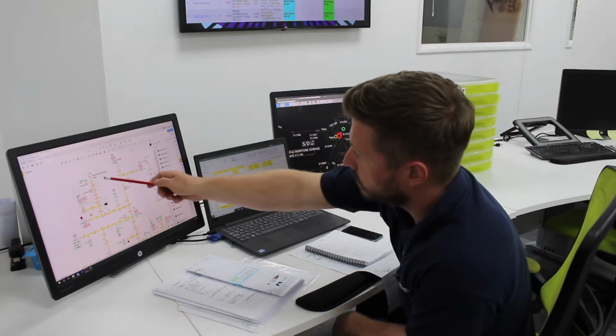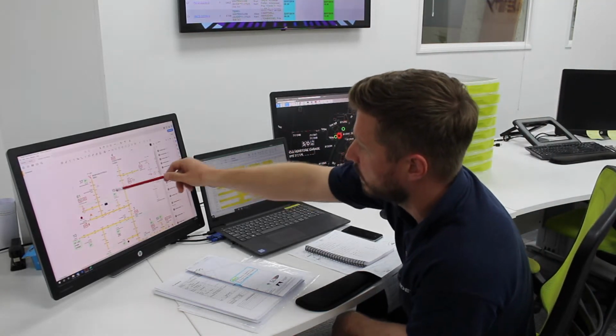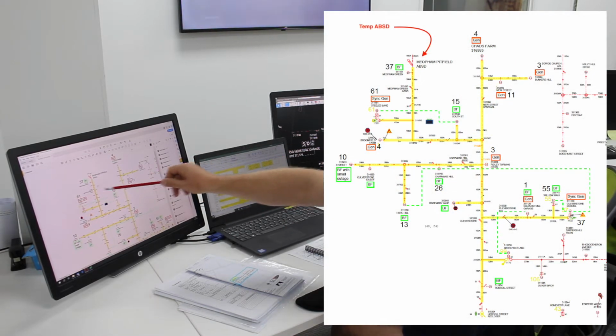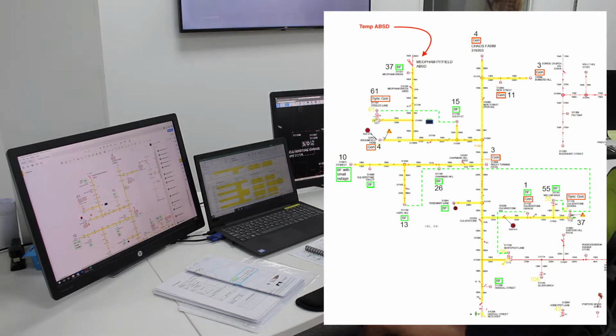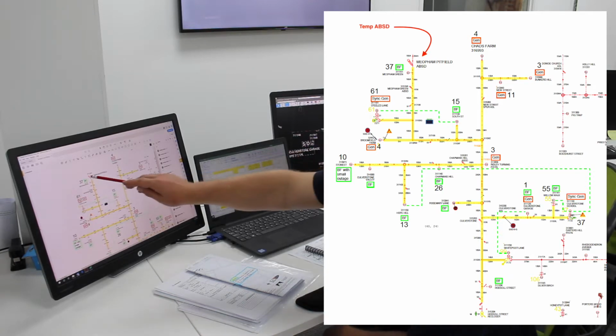The first thing, as you'll see here, we've got a temporary ABSD that's been added to the network. Normally we could have had the next ABSD down as the point of isolation, but that itself is a very high risk pole. So by adding the temporary ABSD, we've negated 37 customers going off supply that are now back feedable from the other side of the new ABSD. If you take a look at it, you can see it's a pretty complex piece of network, where there's a lot of interconnection between subs, a little bit of standard back feeds, and then just basic generation.